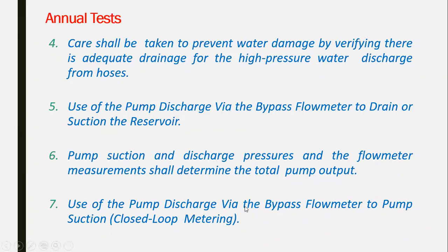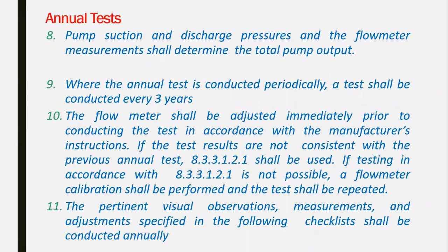Use the pump discharge via the bypass flow meter to the suction for closed loop metering. So this is continuous for the annual test. Suction and discharge pressure and the flow meter shall be determined for the total pump outlet. And when the annual test is conducted periodically, a test shall be conducted every 3 years.